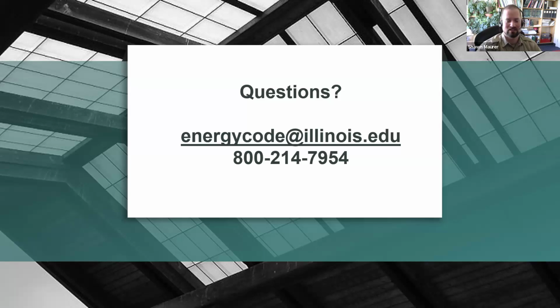Similarly, for time clocks, there has to be an override that can allow them to either be turned on. If the time clock turns them off and someone's still there, they need to be able to override, turn them back on. And then after a couple hours, it resets back to that time clock schedule, or to turn the lights off early if you want to do so. So those overrides are just to provide occupant control if they need something different than what the automatic controls would provide. However, I don't believe there is any language for overrides for controlled receptacles. Not that I am aware of.